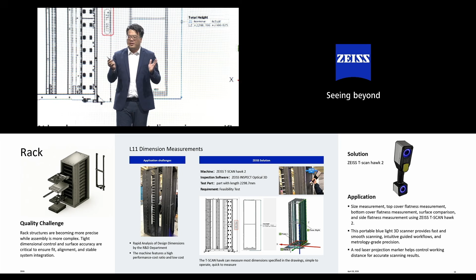Because every single unit of the AI server adds weight, and together they crush and change the deformation of the rack. This means we need a very clear design with a certain shape of the rack, and wait until we put maybe 24 or 27 different units inside, which naturally causes the shape to change back toward the real intended form.